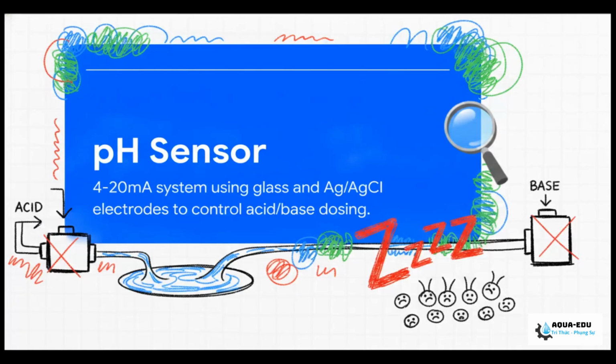Okay, as a quick refresher, our inlet pH sensor is a 4 to 20 milliamp transmitter system. It basically uses a glass electrode and a silver-silver chloride reference electrode to measure hydrogen ions. But why does this actually matter to us on the floor? Well, because this sensor directly controls our acid and base dosing pumps. If this little sensor fails, our chemical dosing goes completely off logic. We end up wasting literally thousands of dollars in chemicals, we completely ruin our coagulation process, and worse, we risk sending a massive pH shock right into the biological bugs downstream.